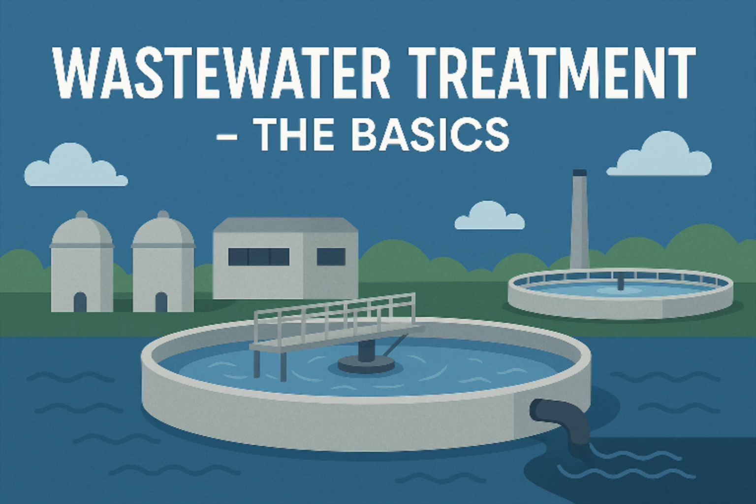And after the bacteria have done their job, the water flows into secondary settling tanks, or secondary clarifiers. Similar to the primary stage, the water slows down again, and this time the clumps of bacteria, now heavy with consumed waste, settle out as sludge. We call this activated sludge. And the water left over is significantly cleaner. We're talking maybe 90–95% free of pollutants by this point. Wow, that's a huge jump in purity.